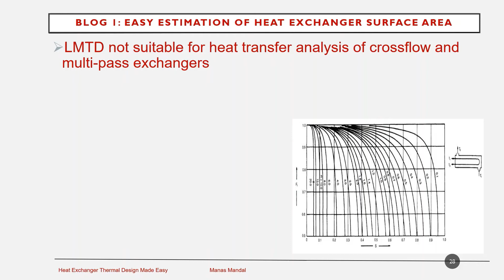LMTD, which we calculated just now, is not suitable for heat transfer analysis of cross flow and multipass exchangers. We need a correction factor which is called F. So when F is multiplied with LMTD, it gives us MTD, and that MTD is multiplied with A and U to give us heat duty. F is a function of two terminologies, S and R, and it is also a function of flow arrangement.